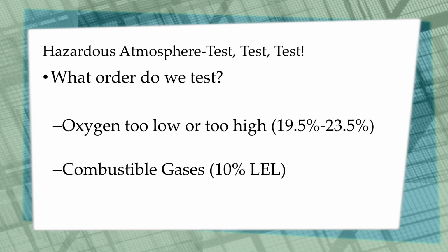As long as you're close to sea level, the oxygen concentration needs to be between 19.5% and 23.5%. Normal atmospheric oxygen is right around 20.9%. If you get below 19.5%, it becomes difficult to breathe. And in fact, too much below it, people breathe out their last breath and they go into convulsions. It's not like holding your breath underwater.